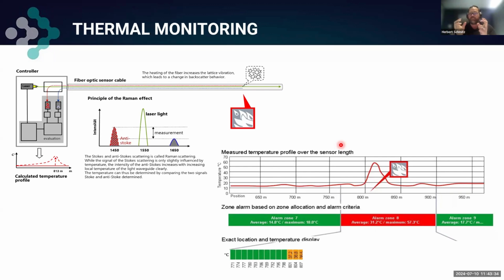Now, if we heat the silica glass and it bounces around, it's like shining a light through a bottle of water and shaking it: we'll see the little bottle of water glows as the light hits those molecules bouncing around. We now shine a laser through that fiber optic cable. That laser hits those molecules and creates reflection. The intensity of the reflection, or what we call backscatter, integrated is our temperature measurement. And the frequency of light throughout the cable is our distance or temperature points. But ultimately, we very accurately see the temperature profile along the entire fiber optic cable.